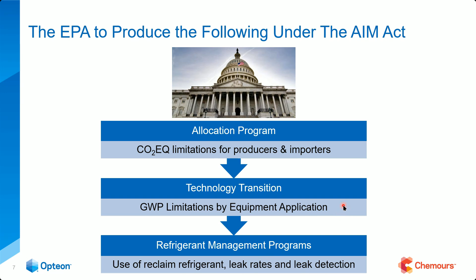The technology transition rule went into effect October 2019, I believe. And this talks about applications. GWP limitations by equipment applications, and whether it's a condenser for refrigeration, whether it's a split system for air conditioning, it has all these different GWP levels that you can't go over or you're in violation. And then the third step is the refrigerant management programs. Its use of reclaimed refrigerants, leak rates, and leak detection. So I'm going to talk about all of these one by one.